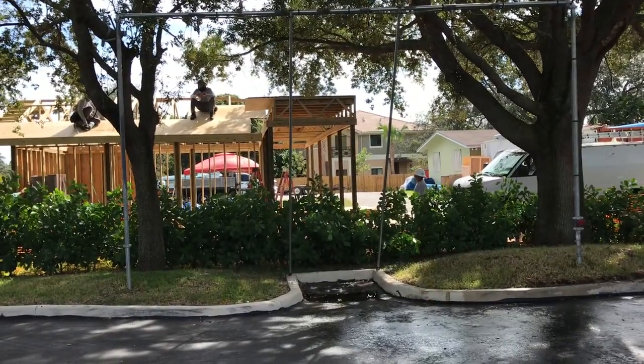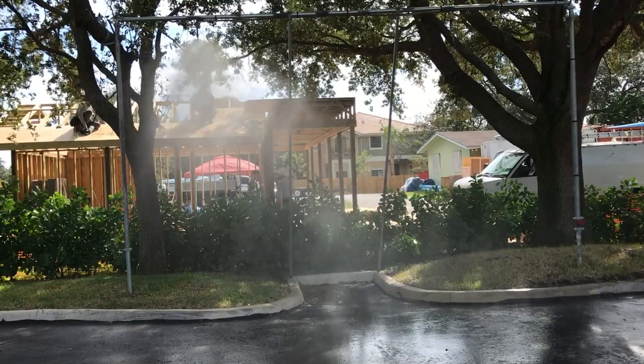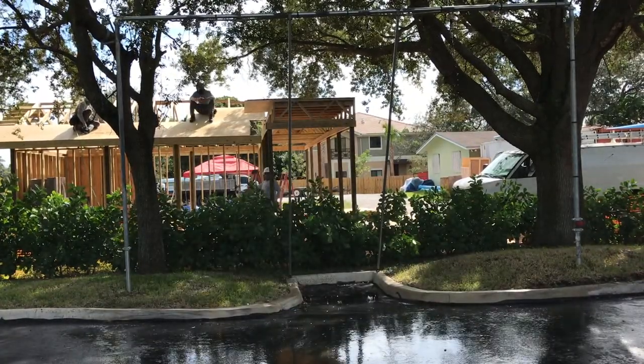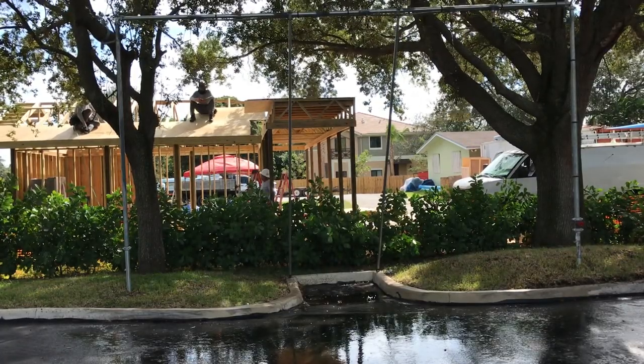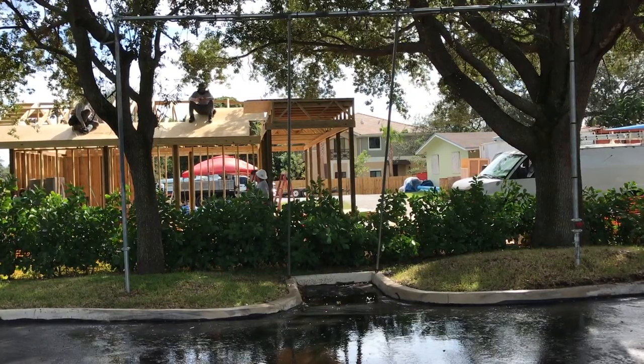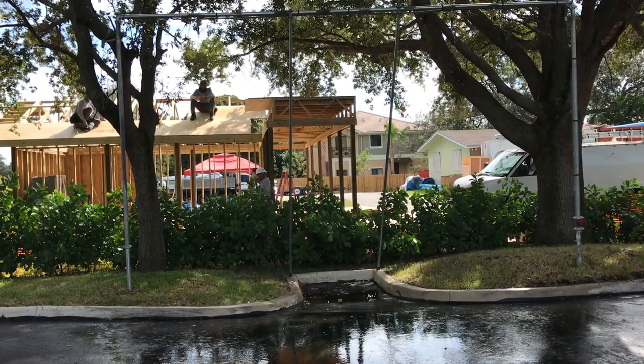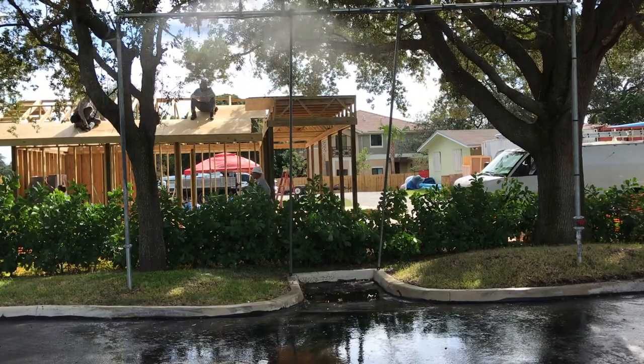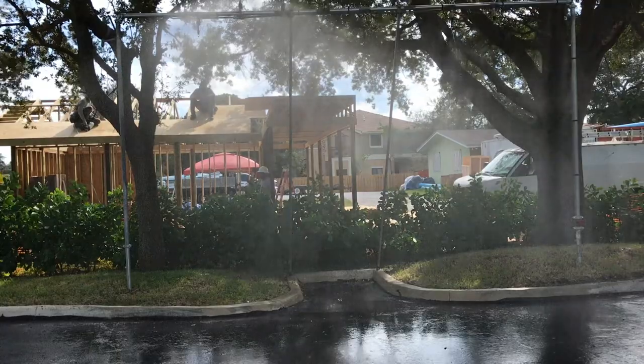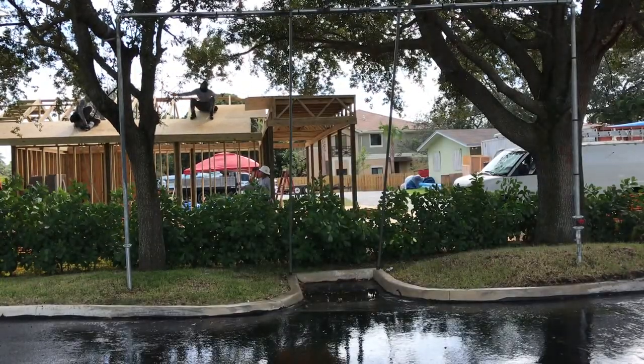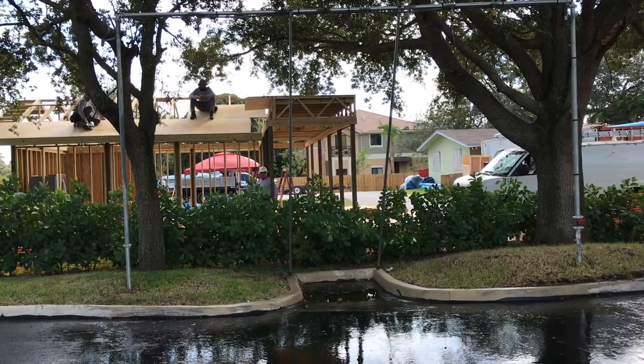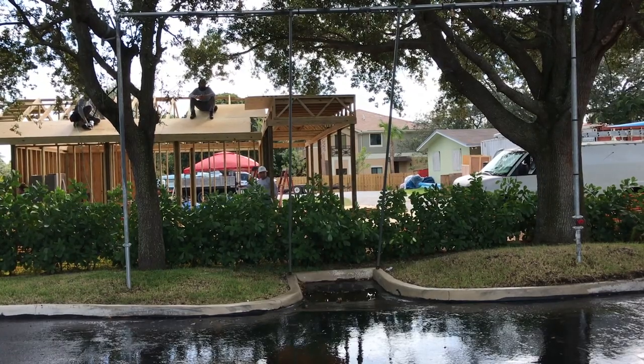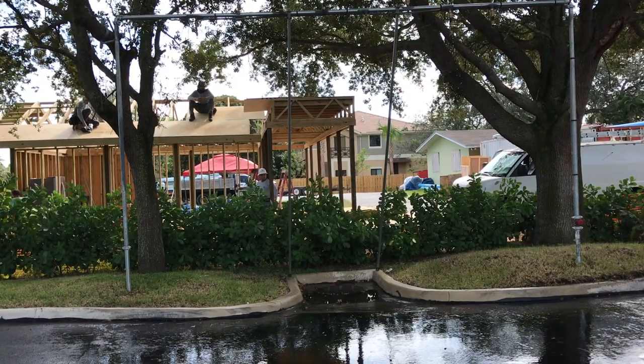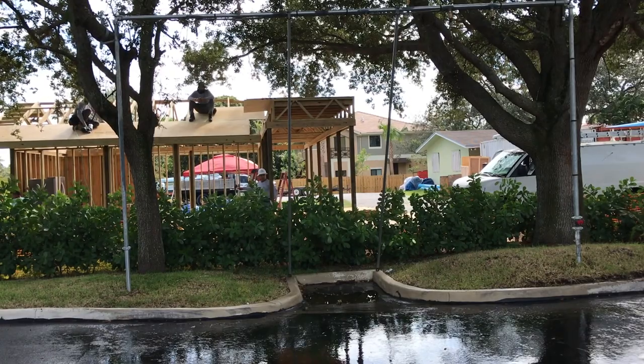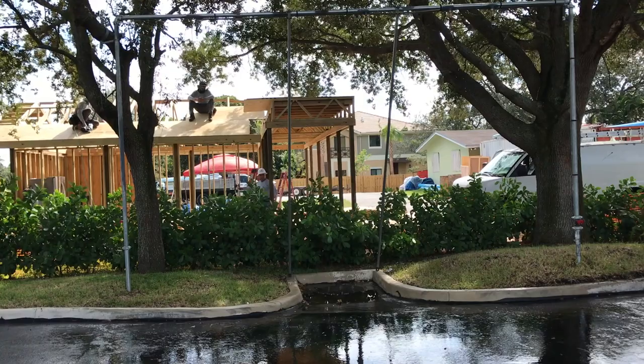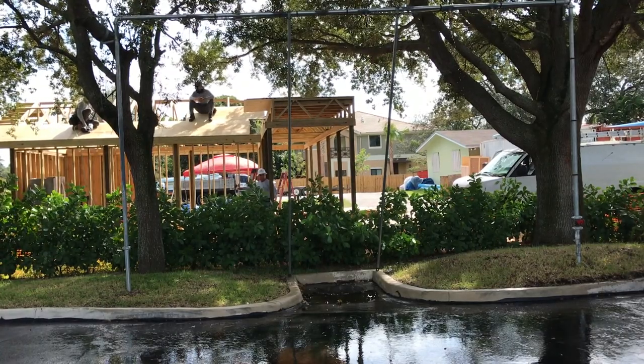Okay, number one, Susie. Perfect. Perfect. Number two is going to be an upright. It's going to flow 26 gallons a minute again at 21.6 PSI. Residential. Number three is going to be a light hazard for light hazard storage. This would flow 20 gallons per minute at 12 PSI pressure. And this head will be a sidewall head. Go ahead, Susie.